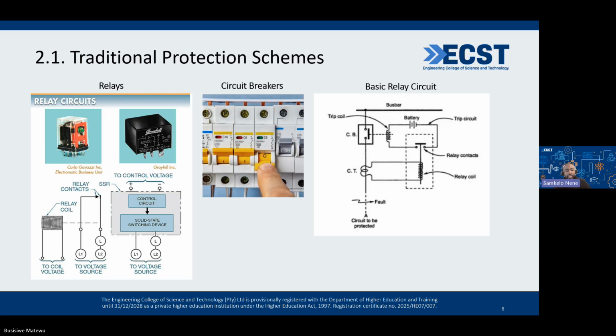For the first one, we see that there is a fault on the third load. If you start from the left going to the right, you see that yellow line like a lightning. It indicates there is a fault. So if there is a fault within the zone of protection of that line, then the circuit breaker that should trip is the one in that zone, because it acts as the primary circuit breaker. Whereas in the second diagram, you see that the main circuit breaker, the one within the protection zone of the generator, trips. That is miscoordination, because it's supposed to be the circuit breaker within the protection zone where the fault is occurring that acts first. If it does not act, then the next circuit breaker can trip.